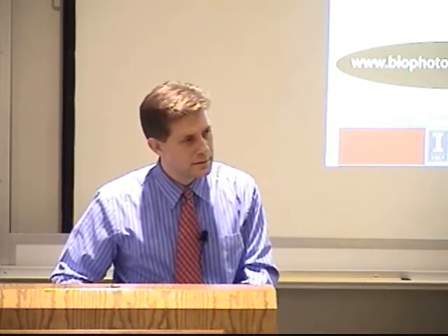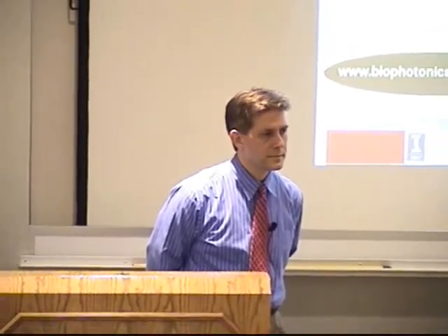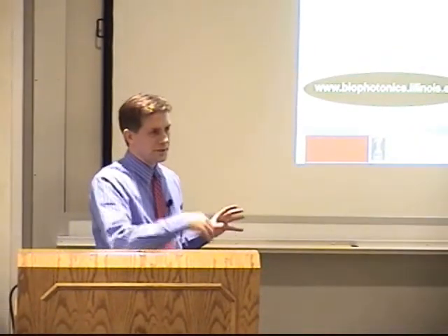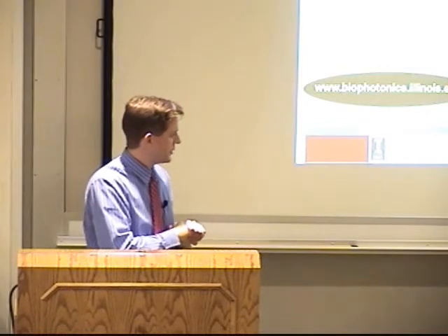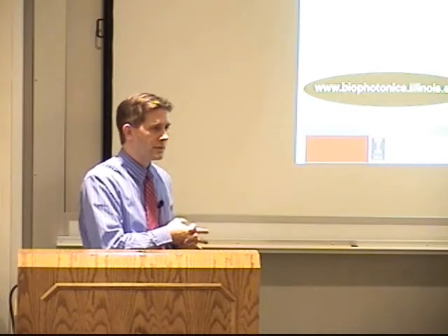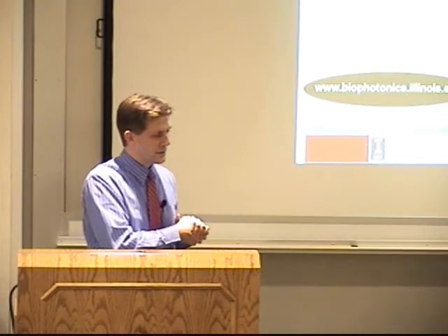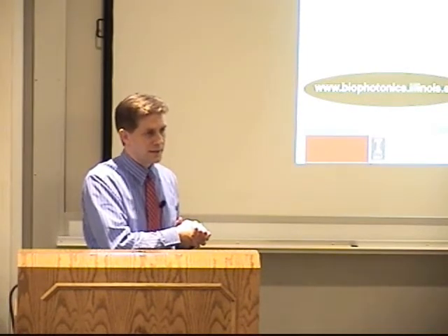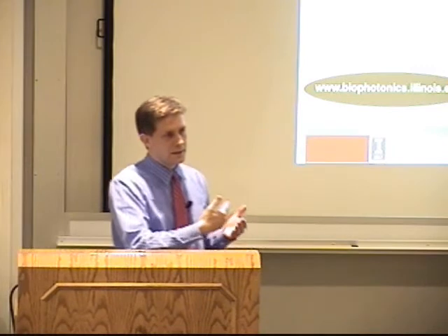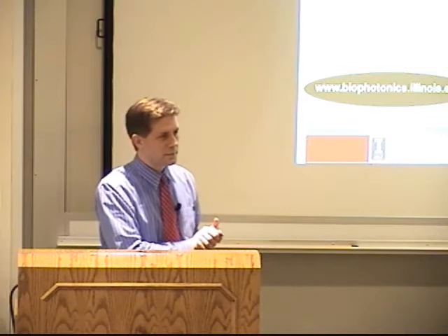I'm just wondering where the deep parallel process is, and how long do the algorithms take now? Yeah. So if we look at the two different modes, OCT and ISAM, as being two discrete things, right now for OCT, we really are limited computationally because the rate at which we can scan these A scans in our systems now is about 30,000 A scans per second. And so that's 30,000 depth scans per second. You can break that up: if you have an image 500 columns across, that's 60 frames per second, or you can divide that up into a volume of data.